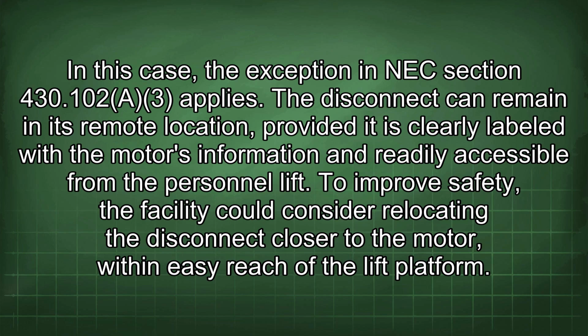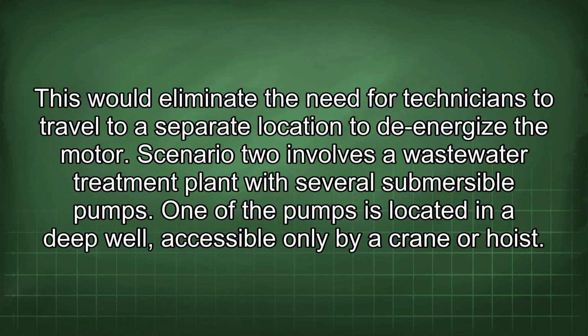The disconnect can remain in its remote location, provided it is clearly labeled with the motor's information and readily accessible from the personnel lift. To improve safety, the facility could consider relocating the disconnect closer to the motor within easy reach of the lift platform. This would eliminate the need for technicians to travel to a separate location to de-energize the motor.